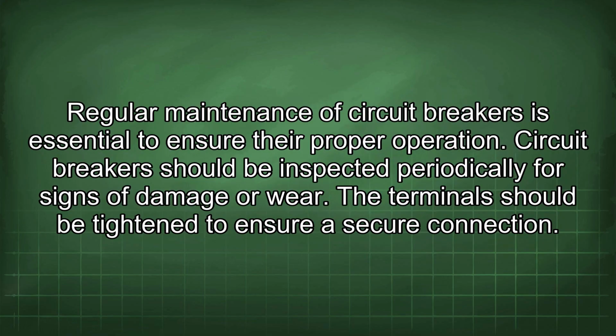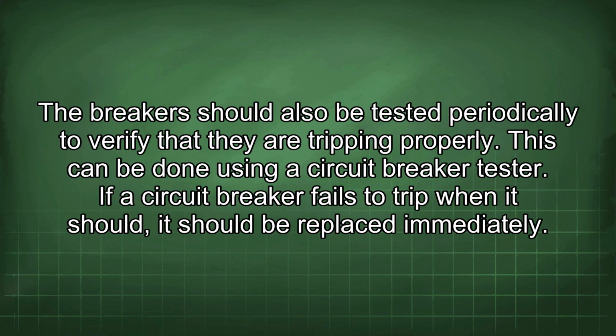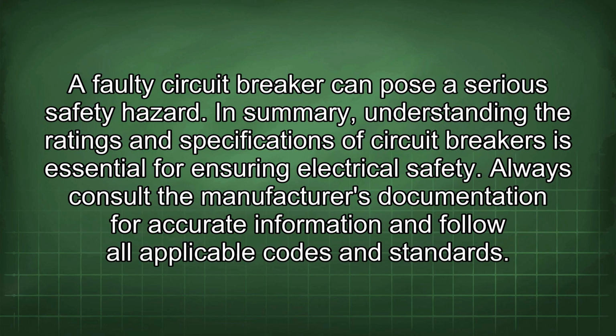Regular maintenance of circuit breakers is essential to ensure their proper operation. Circuit breakers should be inspected periodically for signs of damage or wear. The terminals should be tightened to ensure a secure connection. The breaker should also be tested periodically to verify that they are tripping properly. This can be done using a circuit breaker tester. If a circuit breaker fails to trip when it should, it should be replaced immediately. A faulty circuit breaker can pose a serious safety hazard.